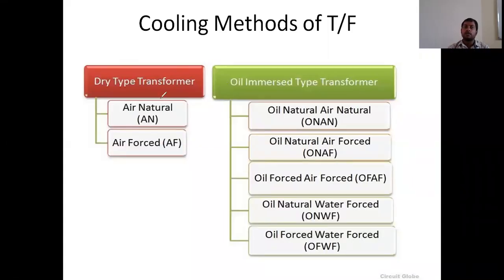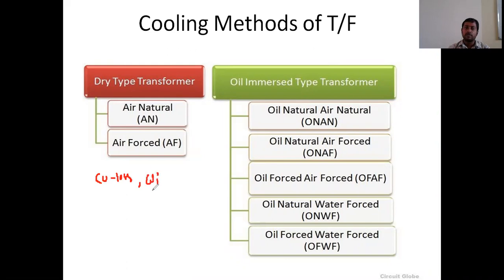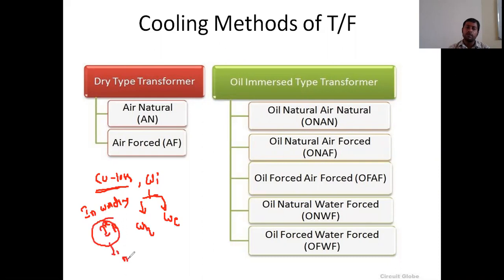In this session I cover cooling methods of transformers. First of all, why do we need to use a cooling system in the transformer? Generally in the transformer, copper losses and iron losses will take place. In the iron losses, hysteresis losses and eddy current losses will take place. Because of the copper losses in the winding, I²R losses are produced, and because of this, heat will be produced.